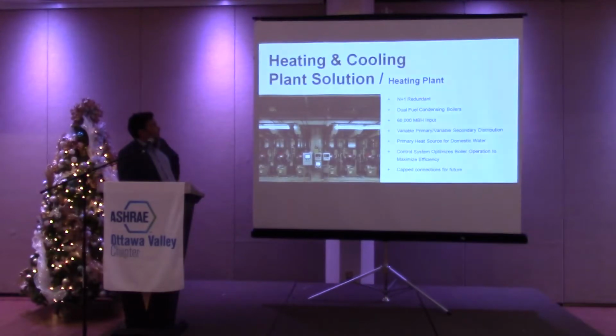So the heating and cooling plant, we have an N+1 redundancy. Again, the heat recovery chillers are actually accounted as part of that redundancy for our heating plant, so we took advantage of that. The one thing about the P3 process is you have to be very competitive, right? Your designs have to be innovative. You have to look for every solution you can to reduce capital cost to make yourself competitive, as well as reduce your energy costs. So that was one of the things that we did, using our heat recovery chillers as part of the redundancy of the plant.